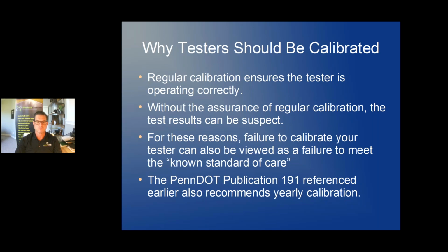If you haven't calibrated your tester in years and there's a problem with the intersection, and someone comes to you and says, okay, let me see your test reports, and then let me see your calibration reports for the tester, that can throw the tester into suspicion, even if you send the tester to us after the fact and we calibrate it or check it and say, yes, it's still within spec. And again, that goes back to the known standard of care that you would be failing to uphold.